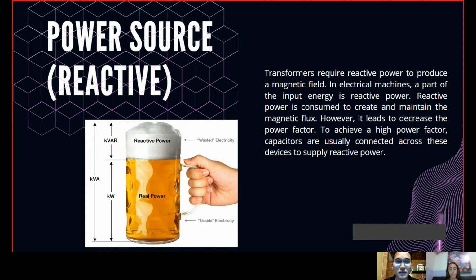Power source reactive. A transformer needs reactive power to produce a magnetic field in electric machines. Part of the input energy is reactive power. Reactive power is consumed to create and maintain the magnetic flux. However, it causes a decrease in power factor. To achieve a high power factor, capacitors are often connected across the device to supply reactive power.